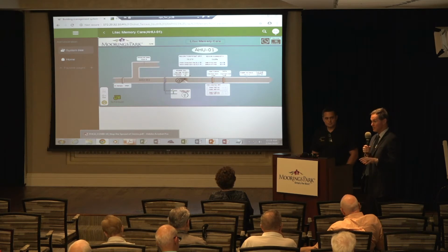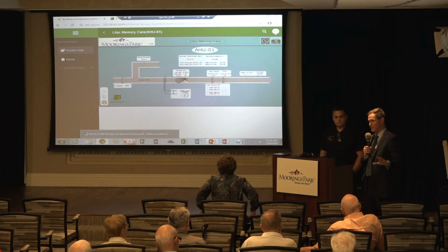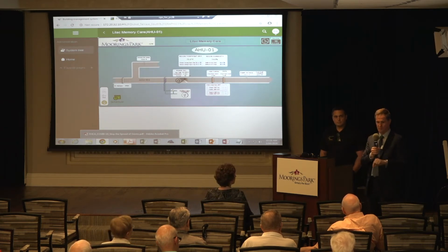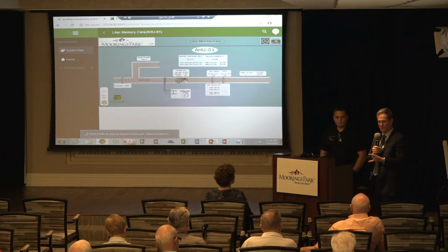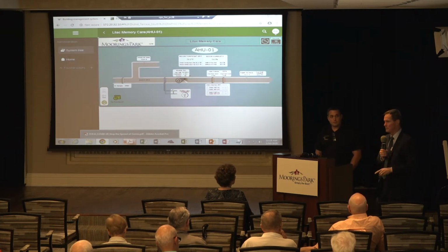In Chateau, when we upgraded — I think everyone's aware of this — we can push the entire load in Chateau once we added that new 1 megawatt generator. ACA requires just emergency circuits, but Moorings Park went above that requirement, and we can push the entire building's entire load, to include I think 96 hours of runtime on fuel.